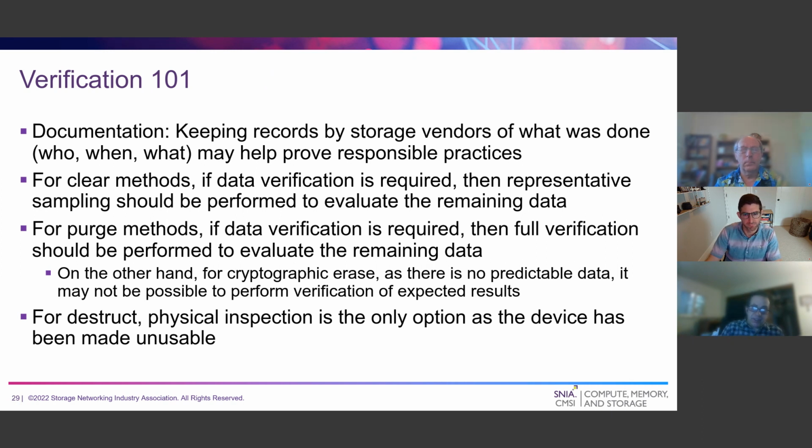When you're checking verification, part of 101, and Jim talked about it a bit, and 2740 talks about it a bit, is you want to keep some records of what was done, what technician did it, when was it done, what method was used, and that'll help prove that you've taken responsible practices to dealing with the data that you're entrusted with.